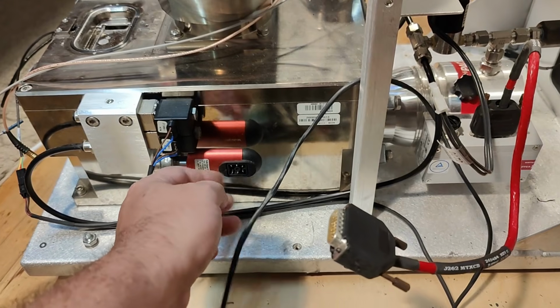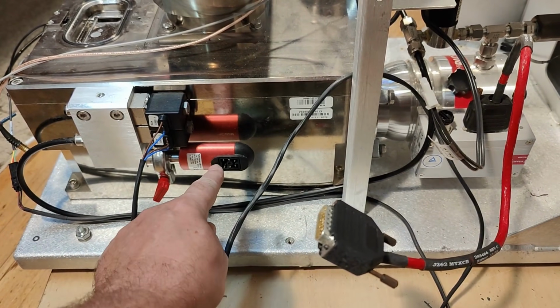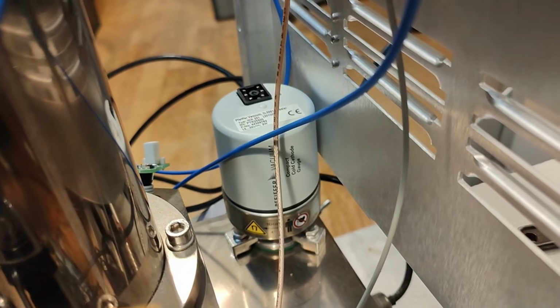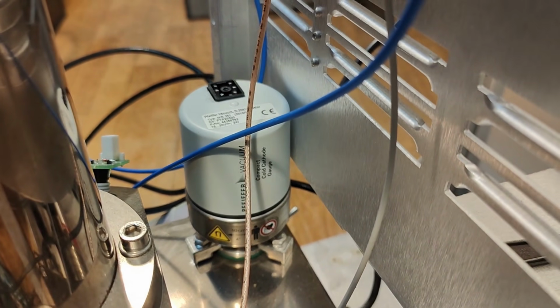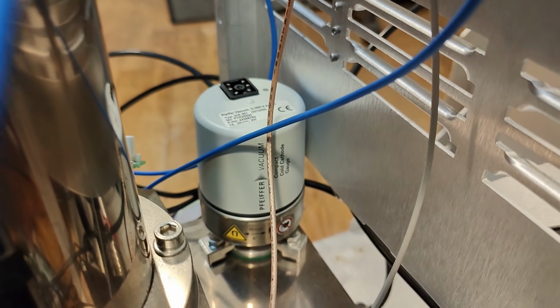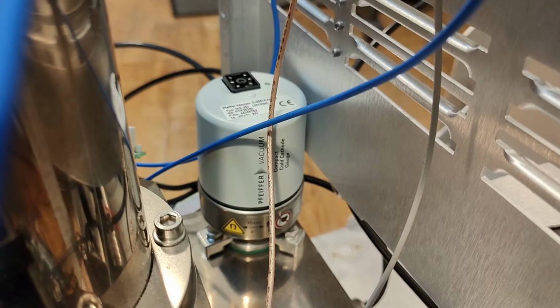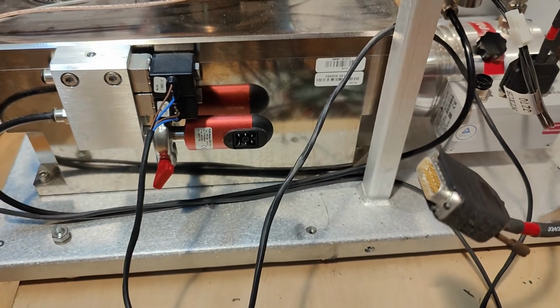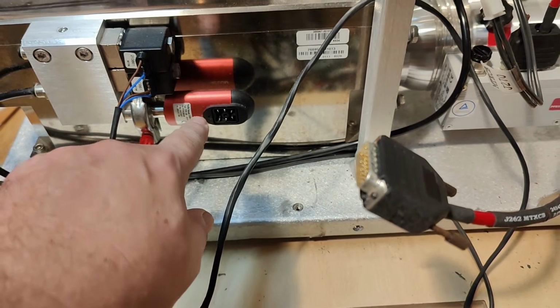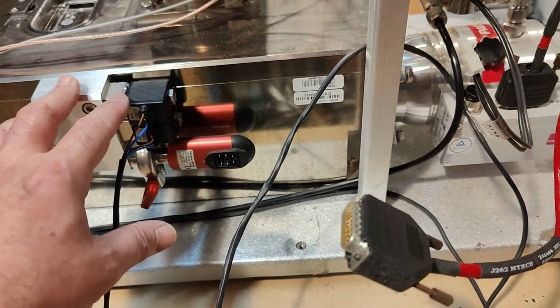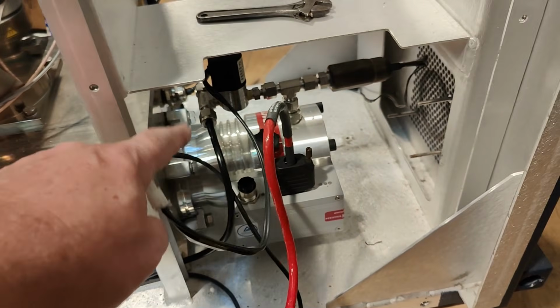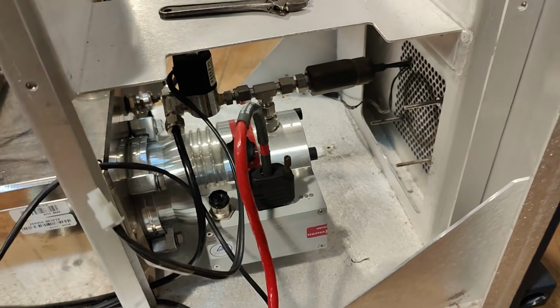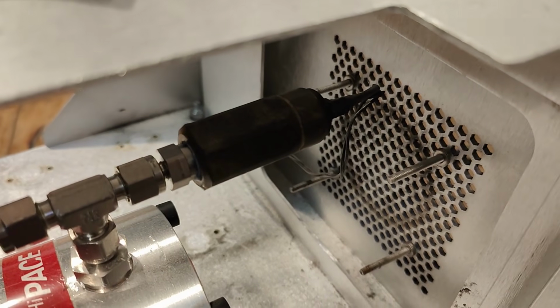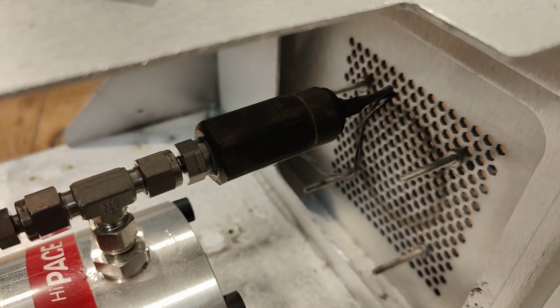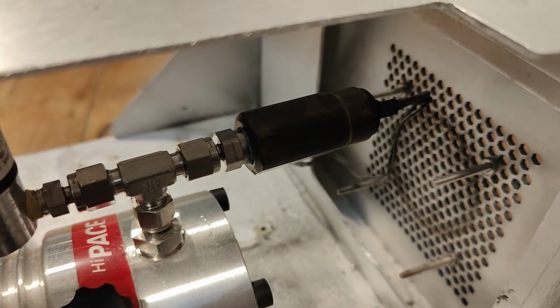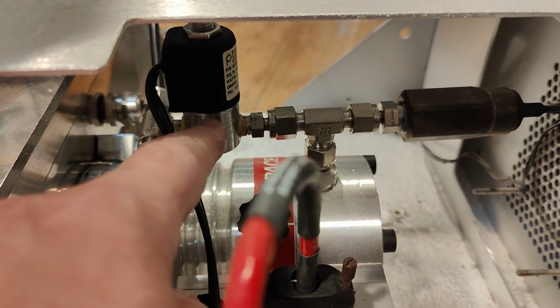And yeah, here's the red sensor. It got the same kind of connector as the other one, and this one is really, really special. I look forward to talking a little bit about that one. They're also quite expensive. So this is the high vacuum sensor, and this is just the low vacuum sensor. And this one is the one that handles all the takeovers from the first pump to the turbo pump. And there's a funny little extra vacuum sensor right here that will just double check that you're not doing anything silly. And then this valve turns off.